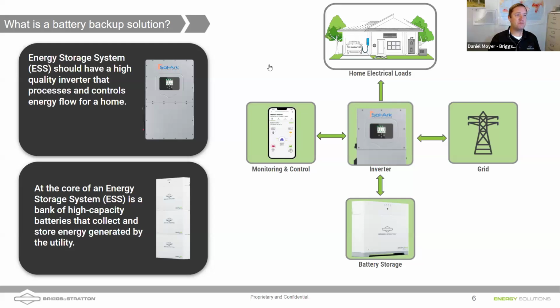Sam's asking, can we please confirm that the SimpliPHI 6.6 will not run on generator backup if utility is still on? So, sorry, Daniel, I have a little bit of trouble hearing you. If you'll go ahead and answer that question. Of course, I'll try to make sure my audio is better. If you do have utility, you're not going to be running the generator. The generator is only there when you don't have enough solar to charge up the batteries and cover the home loads. If you have utility, the utility is going to be responsible for covering the home loads and charging up those batteries. Okay, thank you, Daniel, and I can hear you now.